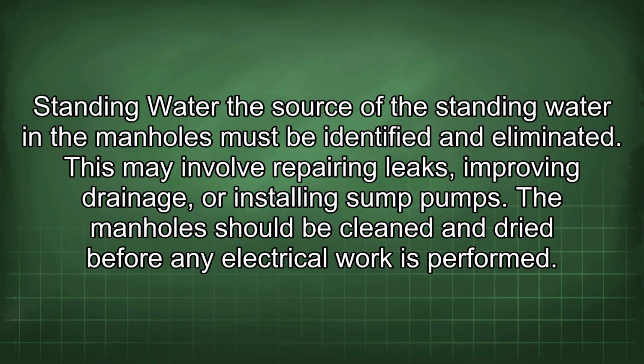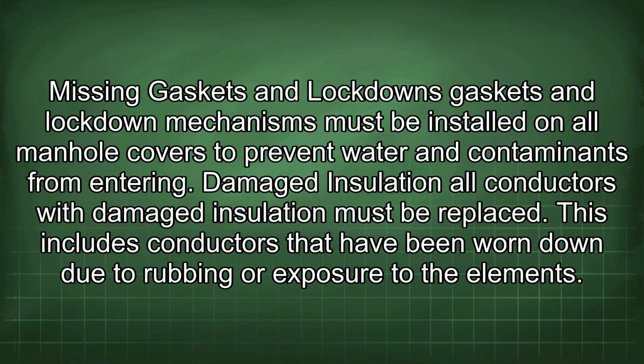Standing water. The source of the standing water in the manholes must be identified and eliminated. This may involve repairing leaks, improving drainage, or installing sump pumps. The manhole should be cleaned and dried before any electrical work is performed. Missing gaskets and lockdowns. Gaskets and lockdown mechanisms must be installed on all manhole covers to prevent water and contaminants from entering. Damaged insulation. All conductors with damaged insulation must be replaced. This includes conductors that have been worn down due to rubbing or exposure to the elements.